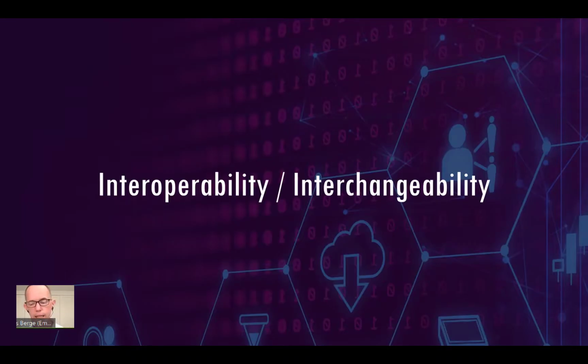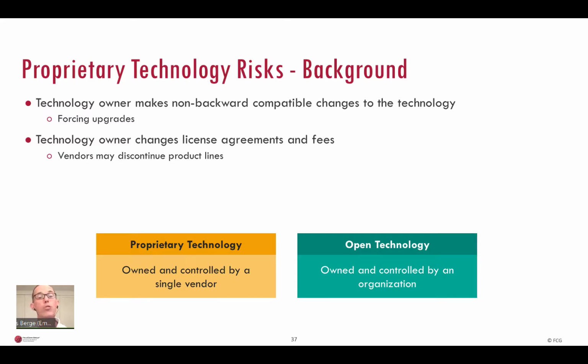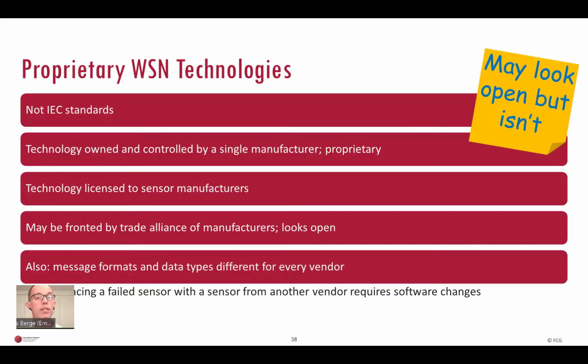Multi-vendor interoperability and standards. There are risks associated with proprietary technologies. For instance, non-backwards compatible changes to the technology forcing upgrades, or changes to subscription models or license agreements and fees that turn sensor manufacturers off, ultimately affecting product and spare part availability as well as their cost. There are wireless sensor network technologies which are not an IEEE and IEC standard. Such technology is owned by a single company. It's proprietary technology. They license their technology to multiple sensor manufacturers, but ultimately the technology is controlled by a single company.